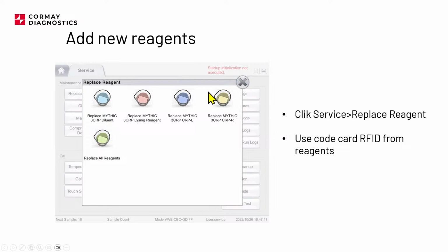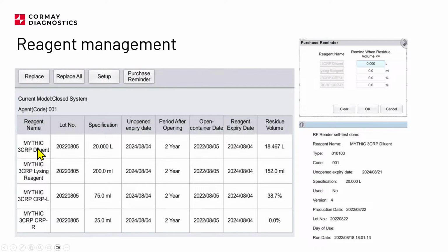As a next thing, the device will show you that reagents are not replaced or that reagents are, let's say, empty. It means that basically there is no information about the reagents. So you need to use a card from your reagent at this point to set up everything on the analyzer, right? So we are taking the card. We are choosing, let's say, diluent from this list and pressing on setup. Then an additional window will appear, and it will say, please place the diluent reagent card on the reader. You just need to place the card there and wait a few seconds.